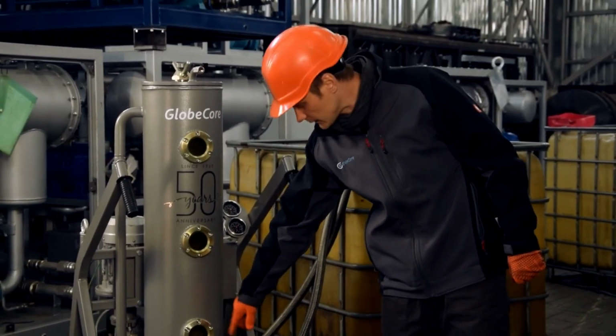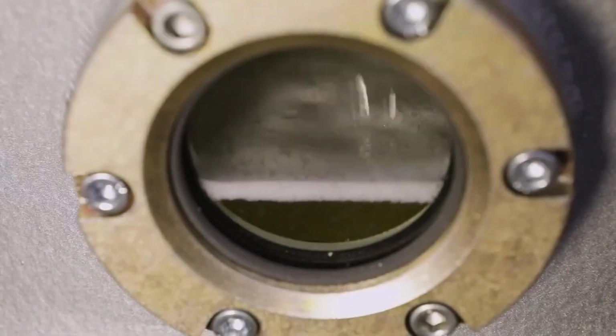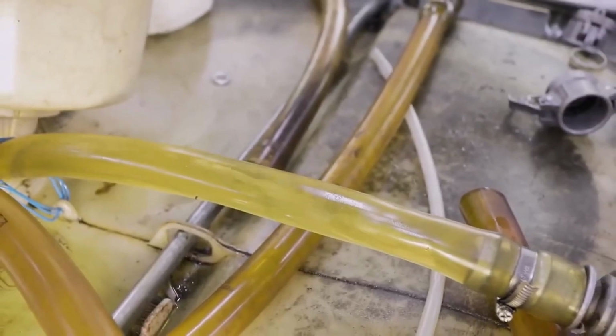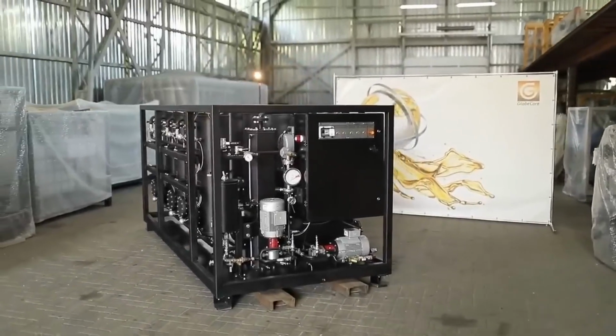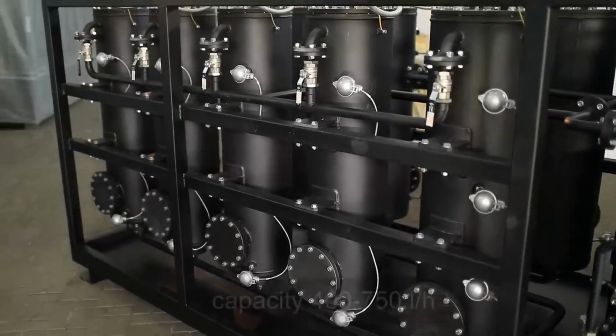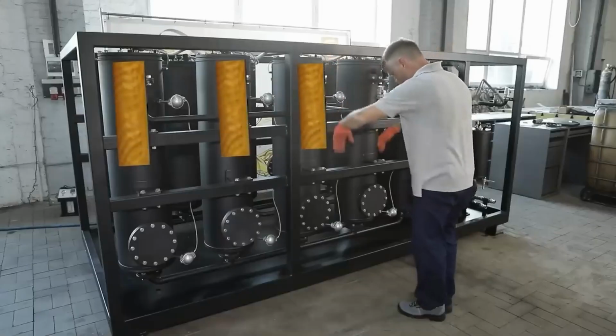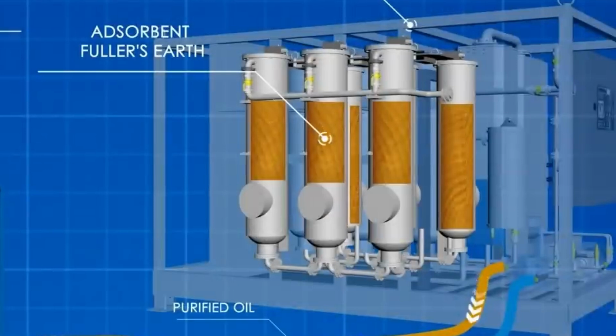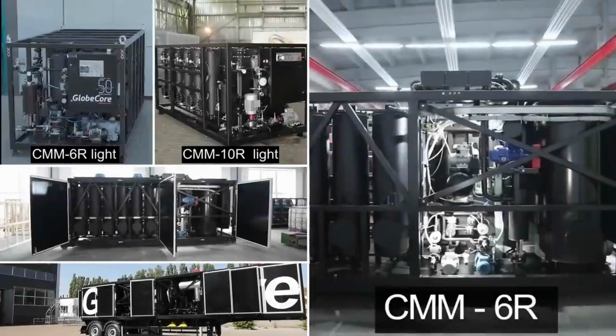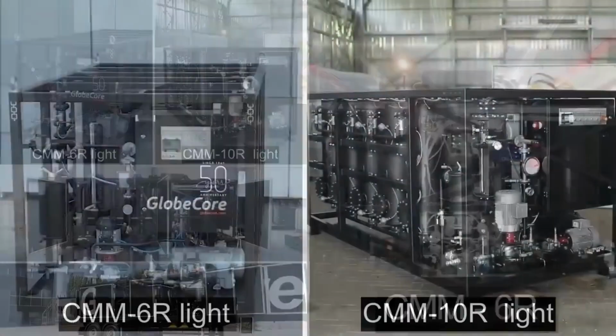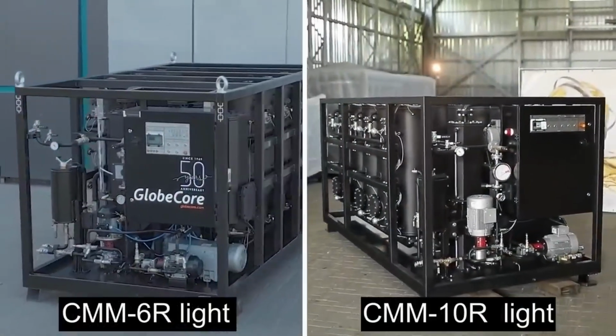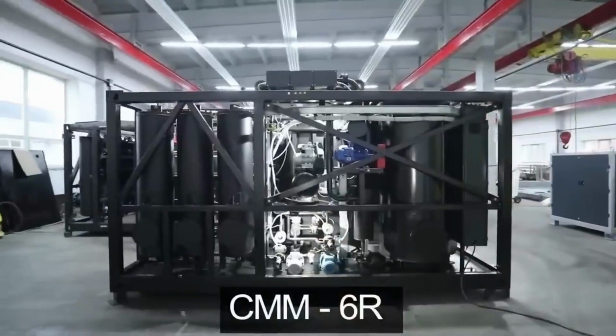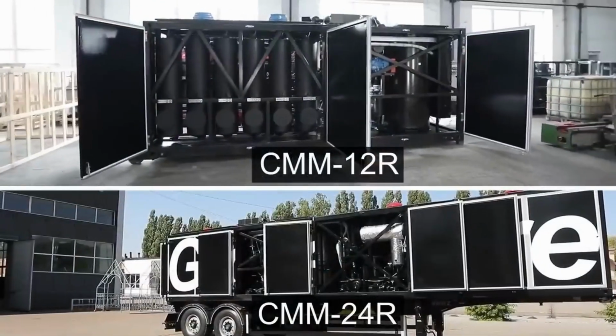At the second stage, the turbine oil is fed into the CMM-R machine where adsorptive purification takes place. Turbine oil is run through the columns filled with a sorbent. Meanwhile, the sorbent absorbs all decomposition and aging products into its granules. If required, after turbine oil regeneration, it is possible to blend in an antioxidant additive. Depending on the model of the CMM-R turbine oil regeneration machine, an antioxidant additive blending unit can be integrated into the machine or used as a standalone item.